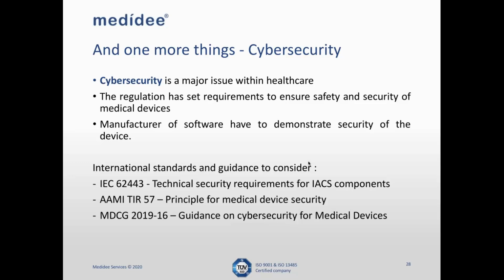Here you have good help. The European Commission has prepared guidance on what to address in cybersecurity for medical devices, and you certainly want to read that guidance when you start your project. But you also have other technical standards which are really useful, like 62443, which gives you a whole family of requirements related to IoT, we can say. And you also have an American standard, AAMI TIR57, which gives you a lot of input for risk management with regard to your software.